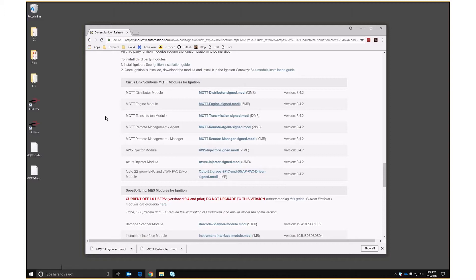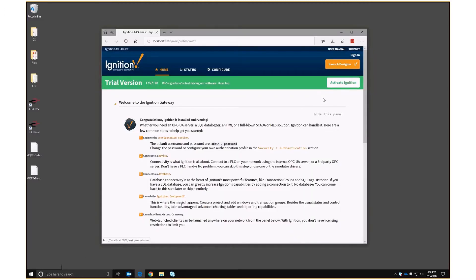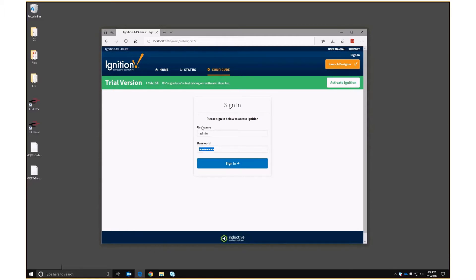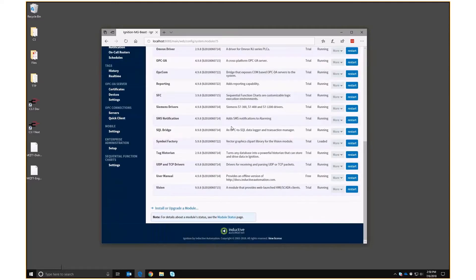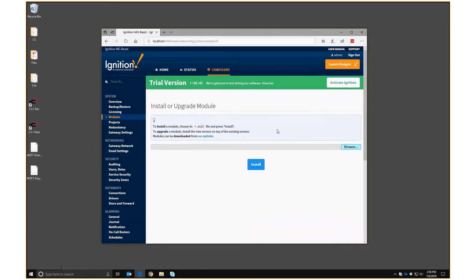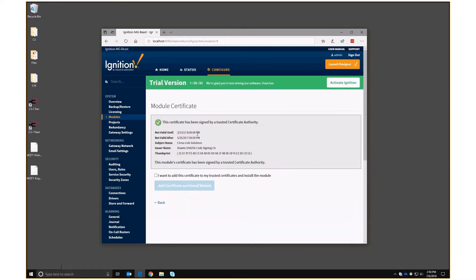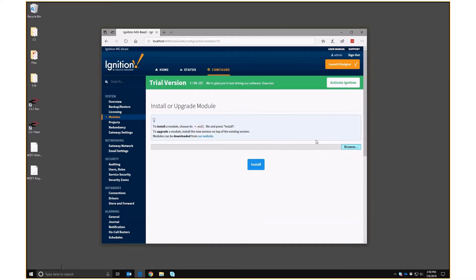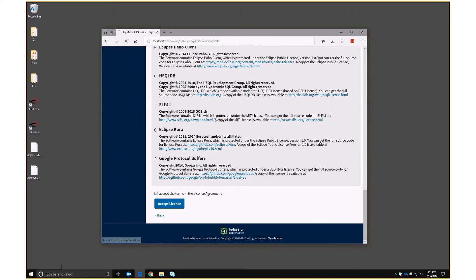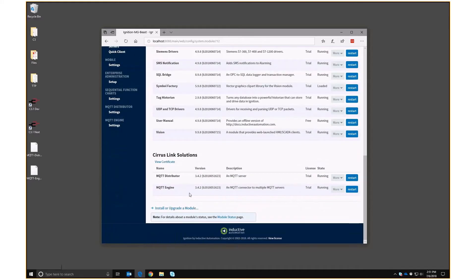Both files are downloaded and virus-checked. We go back to our Ignition web client, go into Configure, and sign in with the default credentials: admin and password. We select 'Install or upgrade a module' at the bottom. We browse to the MQTT distributor, click Install, accept the license and trust the software. Then we do the same for the MQTT engine — accept the license — and that is installed as well.